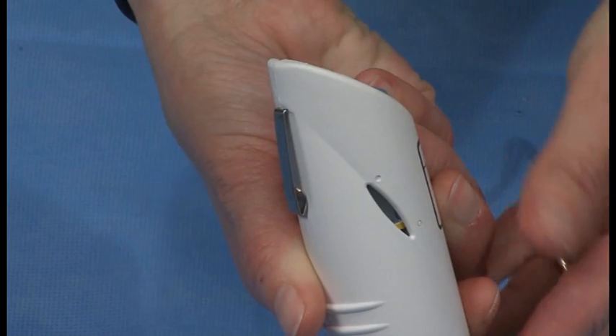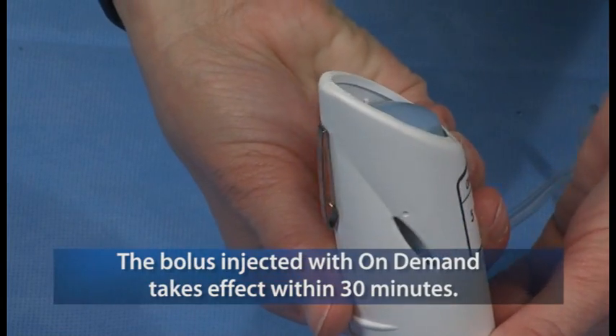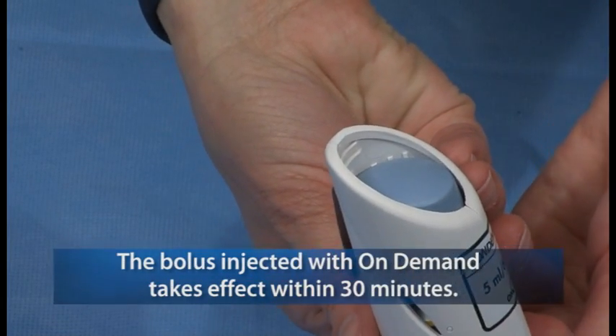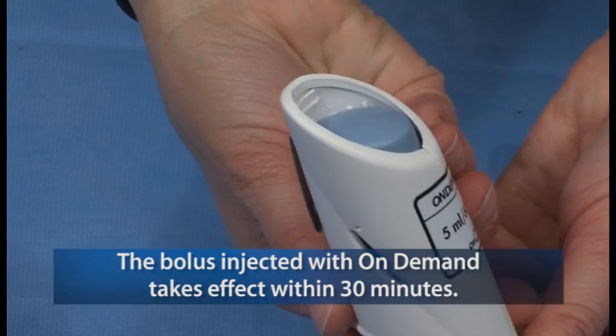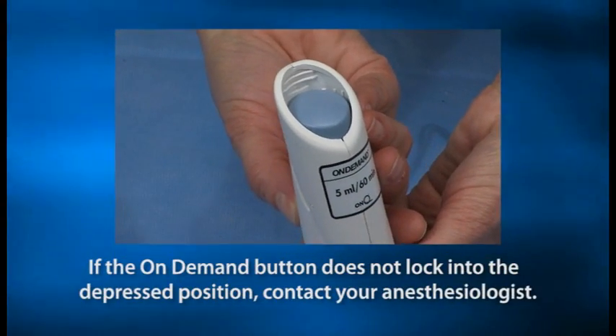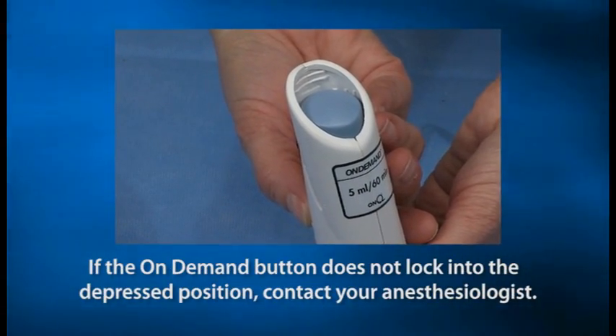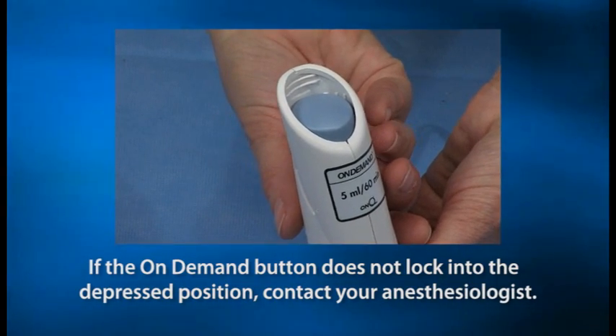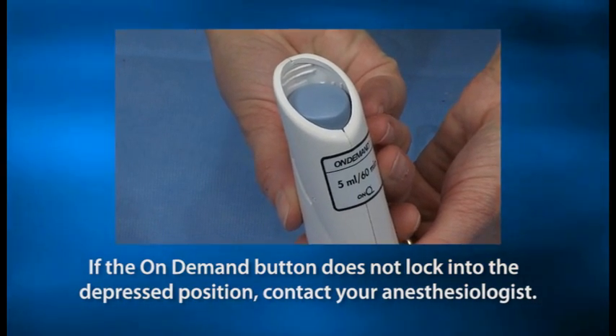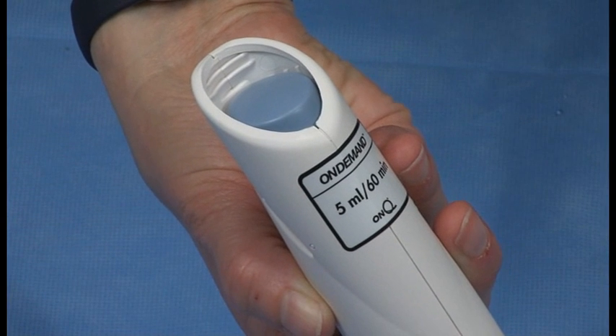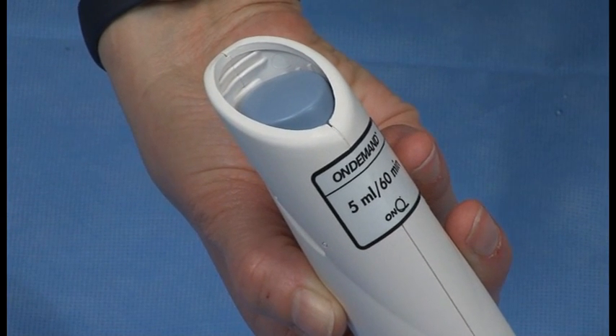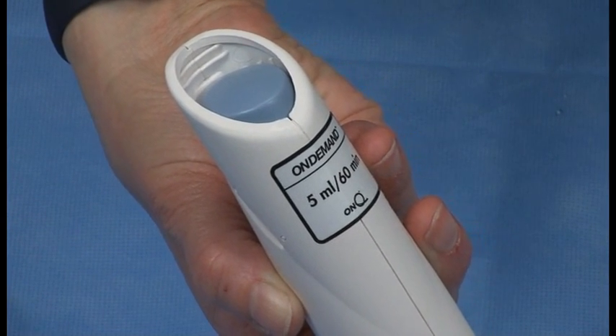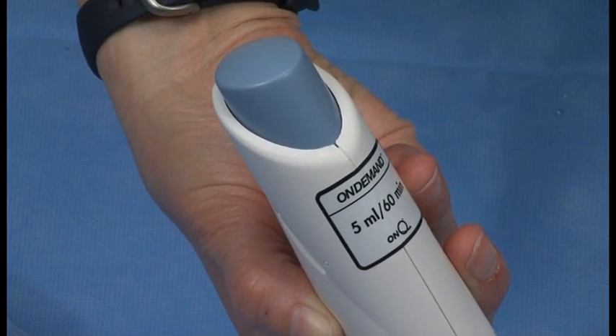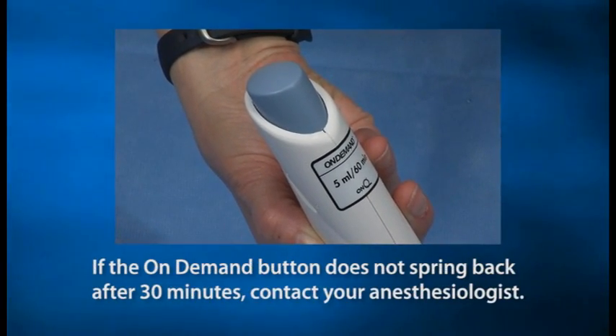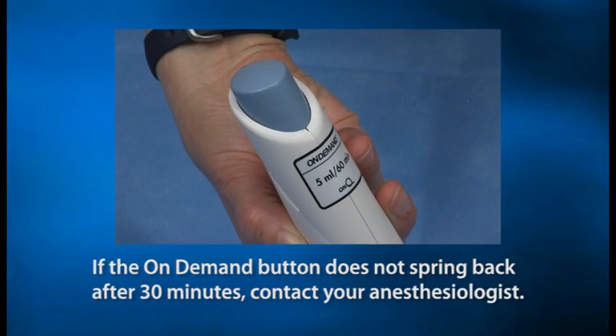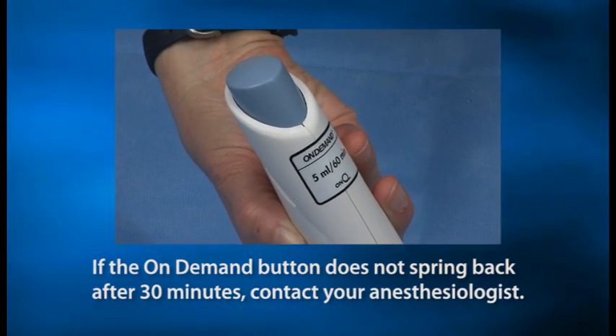The extra dose of medication, or bolus, which is stored inside of the on-demand canister, will be delivered over a short period of time. If the on-demand button does not lock into the depressed position, contact your anesthesiologist at the pager number provided. Once the bolus is administered, which usually takes several minutes, the button springs back to the initial position and the canister begins refilling. If the on-demand button does not spring back after 30 minutes, contact your anesthesiologist.